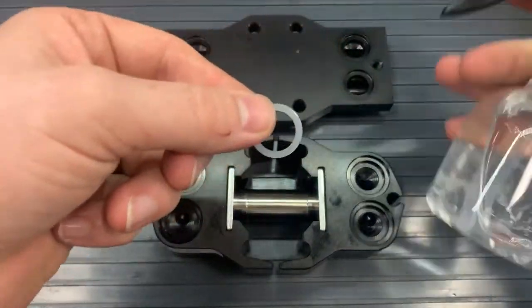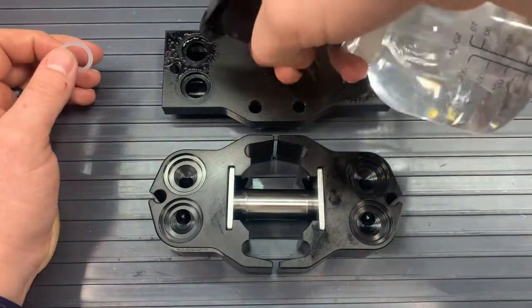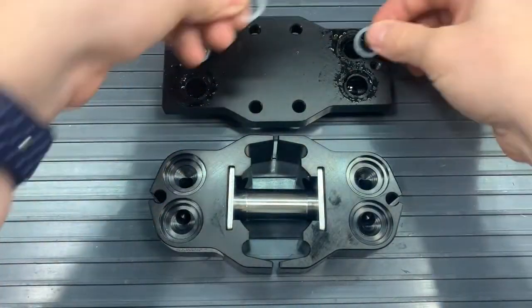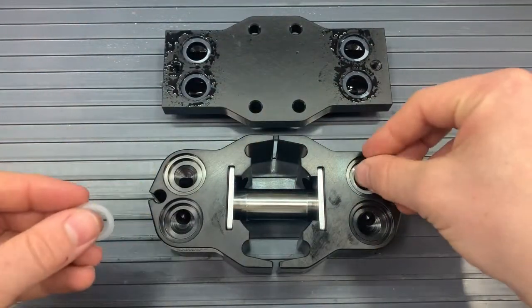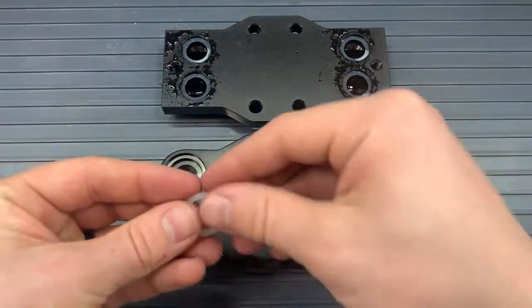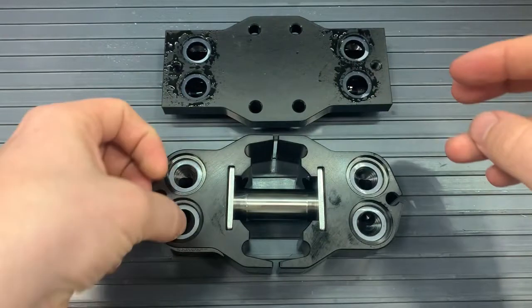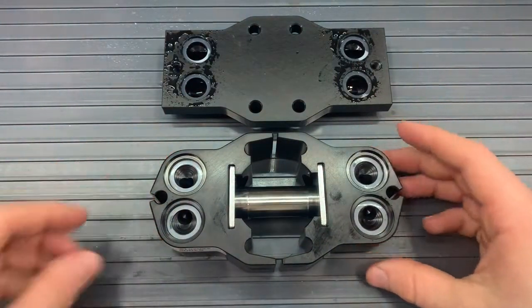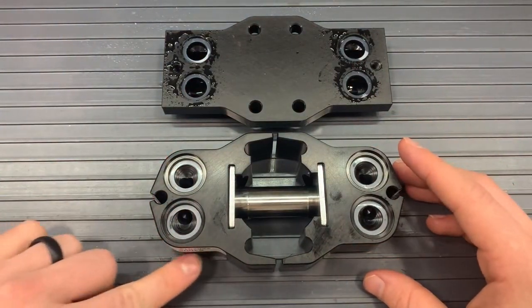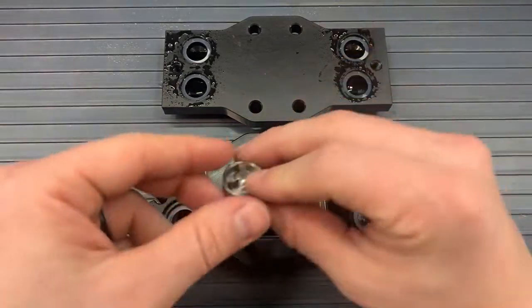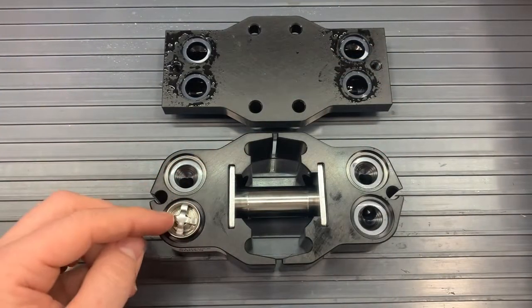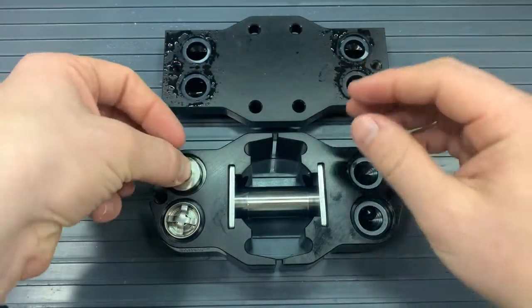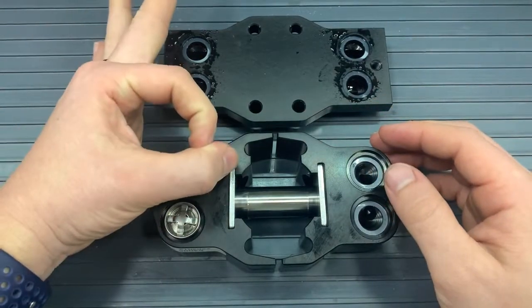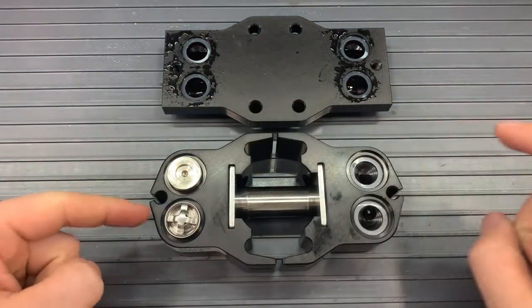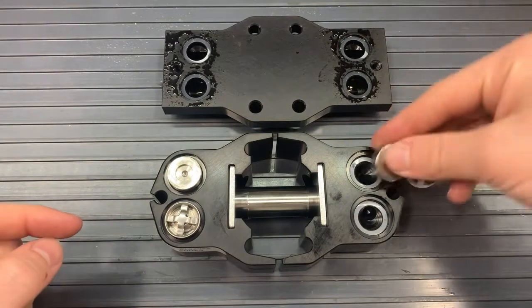These clear washers will go into the pockets in the manifold, 1, 2, 3, 4. And it might be helpful to have a little bit of water to get these to stick when we flip over the manifold. We can put those clear white washers into the valve pockets of the heads. There should be 4 of them. The white washers will be followed by valves, and these valves need to be oriented with the X's closest to that sticker if it is on your pump still. These X's are the outlets, and the O's will be across from each other on the bottom, and these are the inlets. Your water goes in the O's and out the X's.